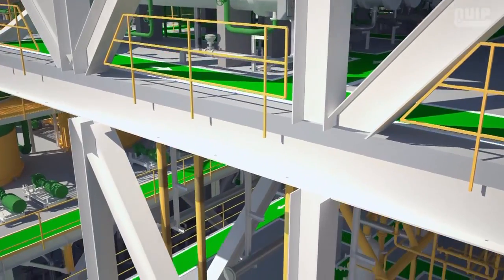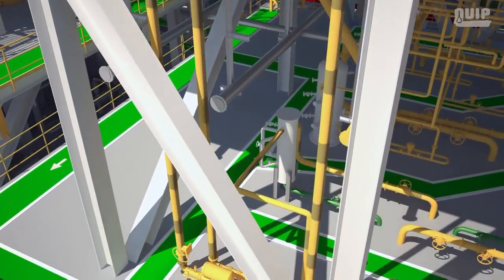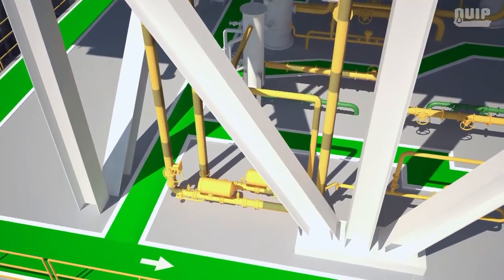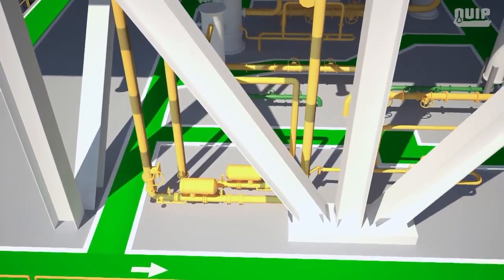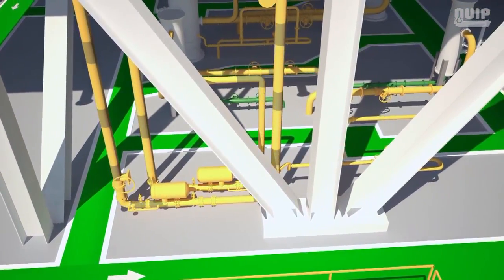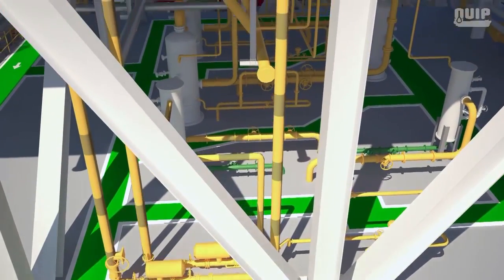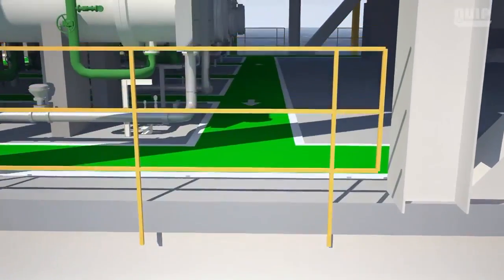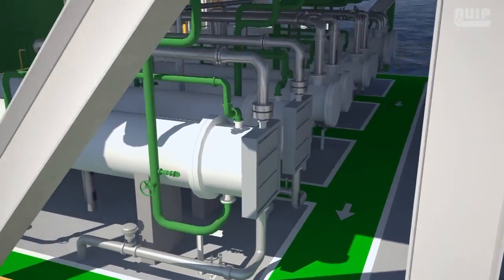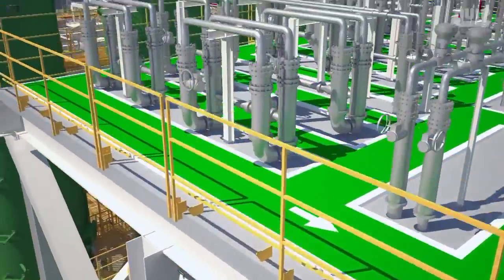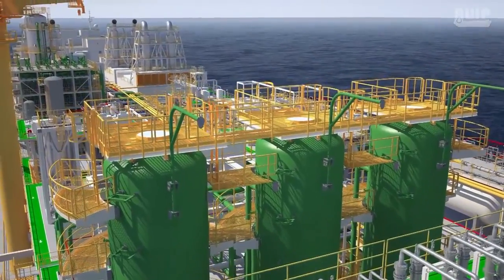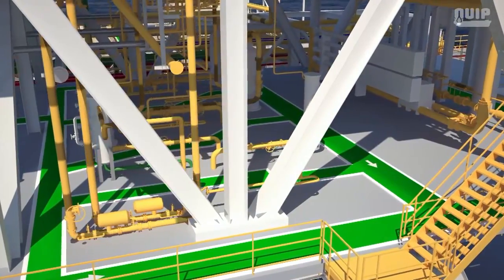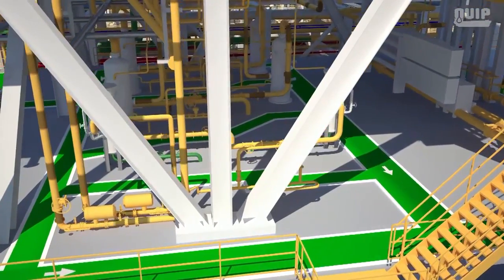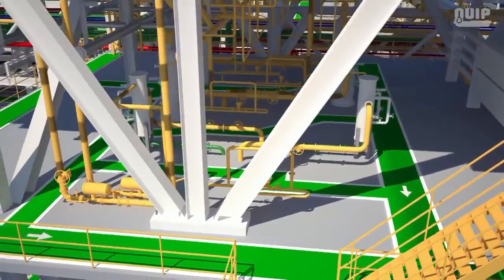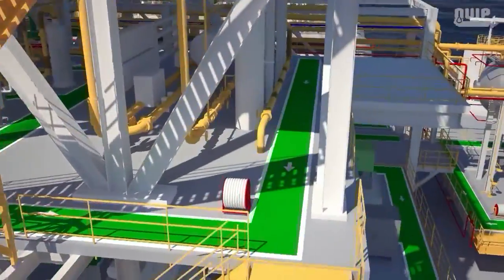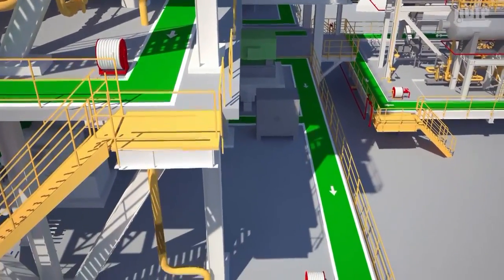Before entering the vessel, the fuel gas goes through Joule-Thomson valves, which considerably reduce the fuel gas pressure. This causes gas cooling, resulting in the condensation of the heavy hydrocarbons. Within the vessel, the hydrocarbons are condensed and the light gas, which is mainly methane, goes to the top. After going through the multi-stream heat exchanger, this light gas is sent to the power generation motors, while the condensed gas from the vessel is reheated and afterward sent to another separation vessel, where it goes to another condensate removal process. It is then reheated before being sent to feed the boilers.